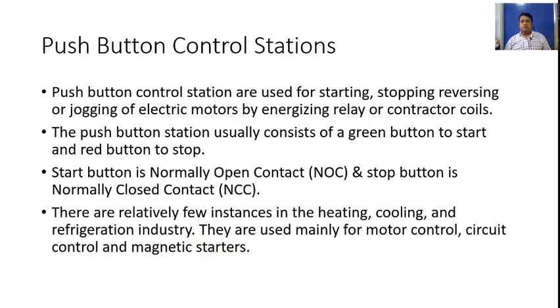Push button control stations. The push button control stations are used for starting, stopping, reversing or jogging of electric motors by energizing the relay or contactor coils. The push button station usually consists of a green button to start and a red button to stop. The start button is normally open, that is NOC, and the stop button is normally closed, that is NCC.